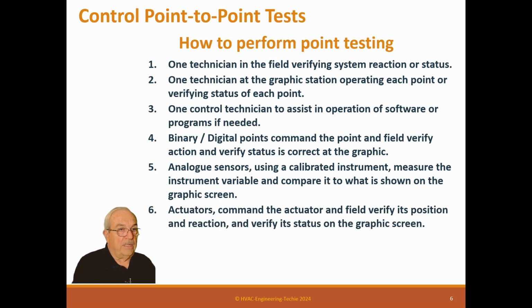Now we talk about actuators. Command the actuator, field verify its position and reaction, and verify status on the graphic screen. Same thing. So if you've got an analog valve, you say, well, run that valve full open, and you can watch it. Now they don't do it instantly, so it takes some time to run up there, and then you say, well, what does it show on the screen? It says 100% open. Okay, great, we're in good shape. Now, you do that, testing both points, and these are all the easy points to do, right? So we do that.